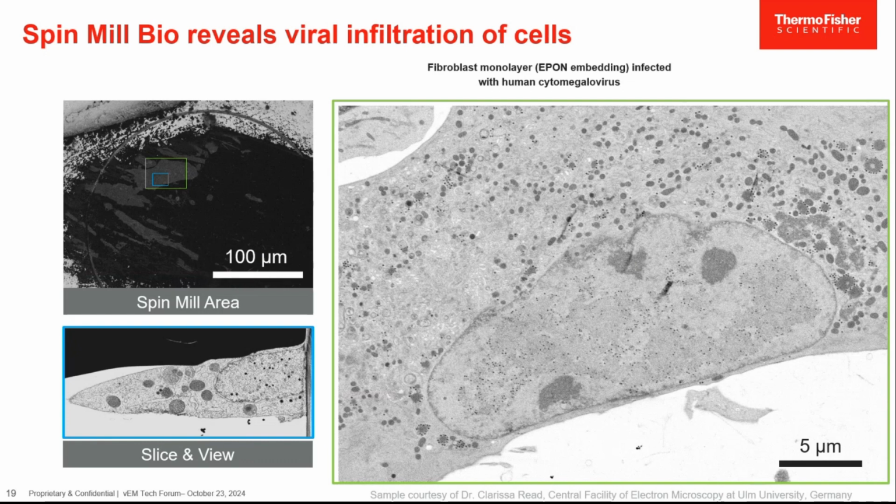If you needed more than a traditional 10 by 10 by 10, if you needed that 5 nanometer voxel, you have the ability to rotate your sample 90 degrees, put down that platinum pad if you like, and image down at about 5 nanometer voxel. So I like to think of this tool as that complete offering for volume in SEM, whether it's AT, traditional FIB, or even the serial block-face-like approach.